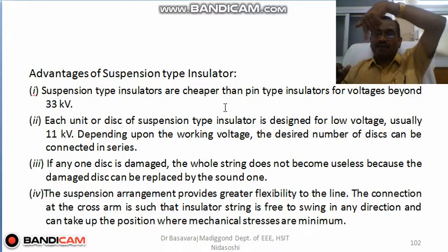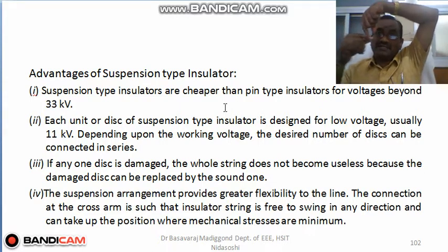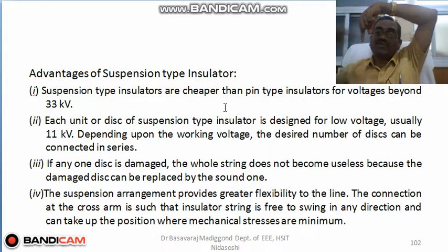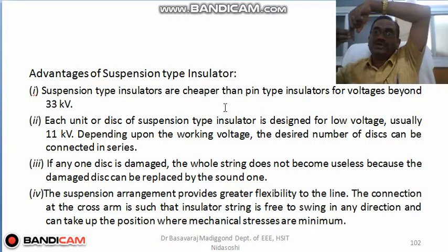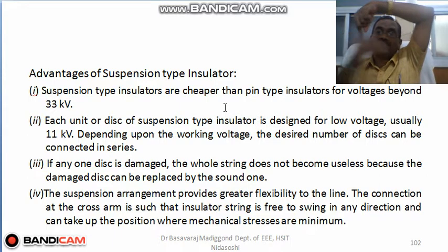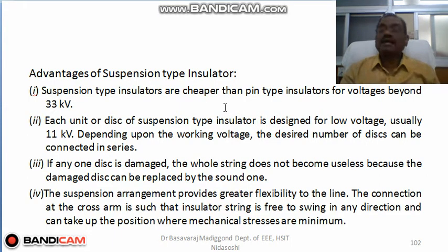For example, if this is the string of insulators, this is suspended. If it is secured or fixed onto the cross arm and is not free to oscillate, then it will suffer the maximum stress when the wind flows. Usually wind blows perpendicular to the string. Therefore, if it won't move, then it has to suffer a high tension. Therefore, it is made free to oscillate. So whenever the wind blows, it will take a position where the tension or stress is less. Okay.